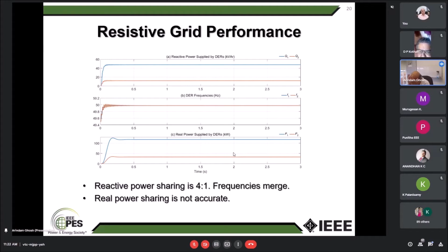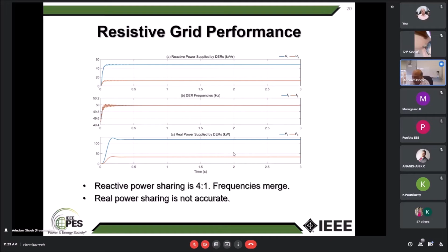Previously, when we have an inductive line, everything is good. You select frequency versus P and Q versus voltage. Now the power sharing is very accurate, as a result of which frequency matches. When you have a resistive grid, your reactive power sharing is accurate, but your real power sharing is not good. So you will say, okay, I want the real power sharing to be more accurate, I can have a little bit of inaccuracy in reactive power, but not in real power. So what do we do?